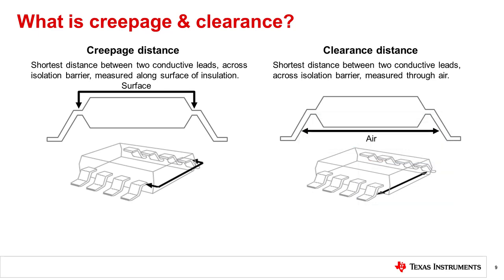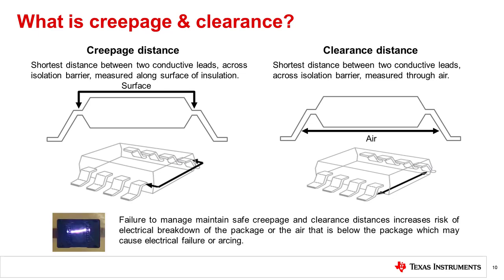Both of these parameters are important because when an electric field is present across the isolator, electrical breakdown of either the package or of the air below the package can cause electrical failure or even arcing. Minimum creepage and clearance distances are defined by the IEC standards bodies as guidance intended to prevent air arcing during operation.